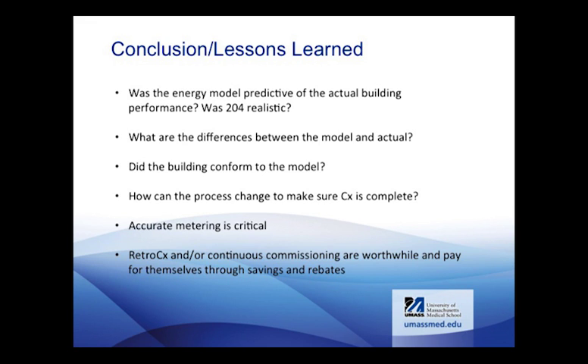And then continuing with retrocommissioning, continuous commissioning—does it pay back? We've seen that it does. We've gotten significant utility incentives for this, and the paybacks tend to be under a year, which is always good when you're pitching this. We're beginning to move forward with continuous commissioning as well, bringing in fault diagnostics, and reevaluating some of these building systems to better understand how it relates to our initial energy model. And that is it.